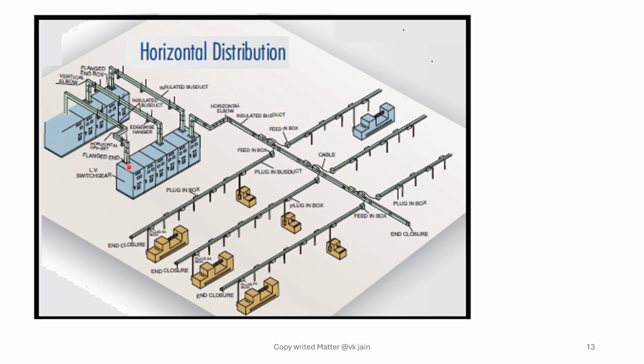So this shows the panel and horizontal distribution bus bar system, which is known as the overhead bus bar system. This is the main bus bar system from where branch lines are also fed like this: one, two, three, four, five, six.